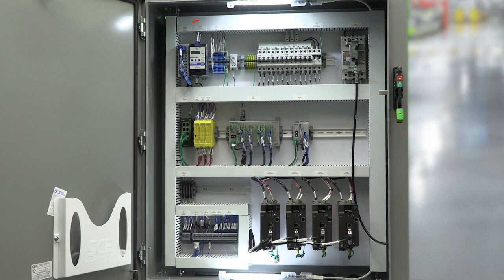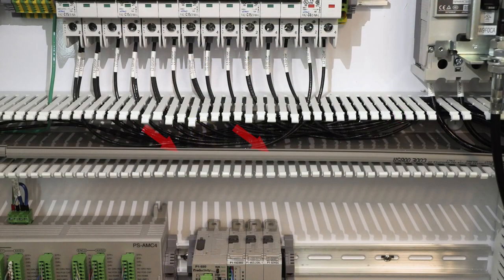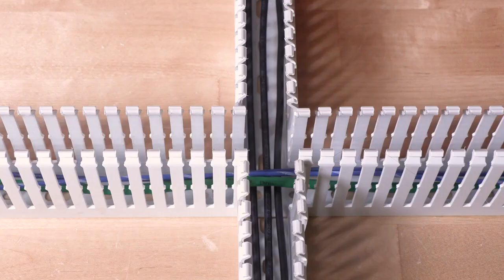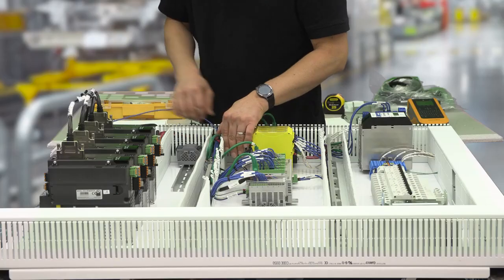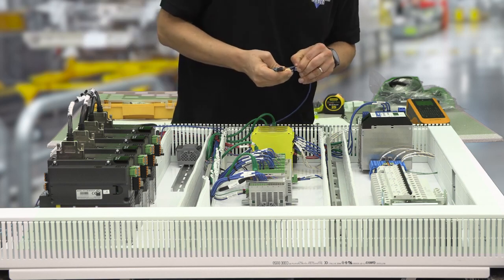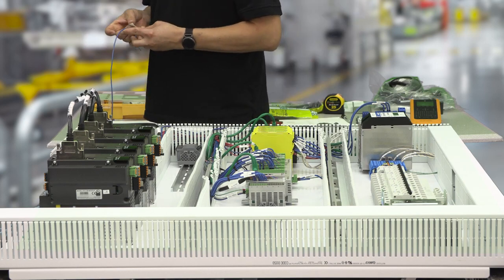The power feed to our DC power supply is the only higher voltage run that goes to the left, and since it must live in the same section of wire duct as some lower voltage wiring, a section of duct separator is installed. If there are locations where high and low voltage wires need to cross, be sure they cross at a right angle. This will reduce inductive coupling, which can introduce noise or signal fluctuations on wires nearby.